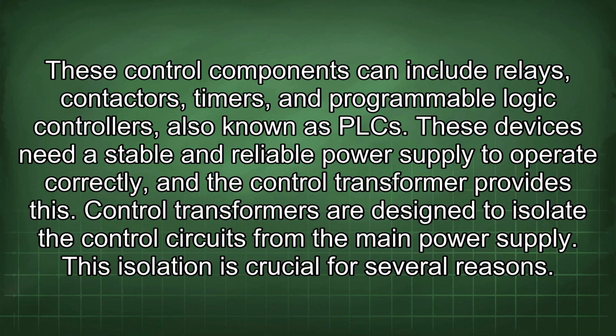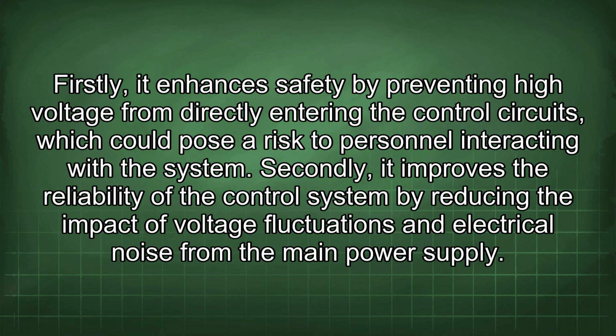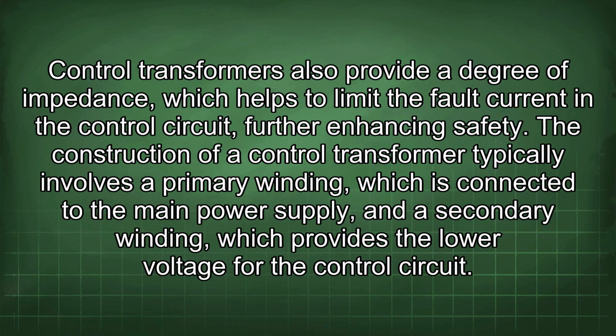Control transformers are designed to isolate the control circuits from the main power supply. This isolation is crucial for several reasons. Firstly, it enhances safety by preventing high voltage from directly entering the control circuits, which could pose a risk to personnel interacting with the system. Secondly, it improves the reliability of the control system by reducing the impact of voltage fluctuations and electrical noise from the main power supply. Control transformers also provide a degree of impedance, which helps to limit the fault current in the control circuit, further enhancing safety.